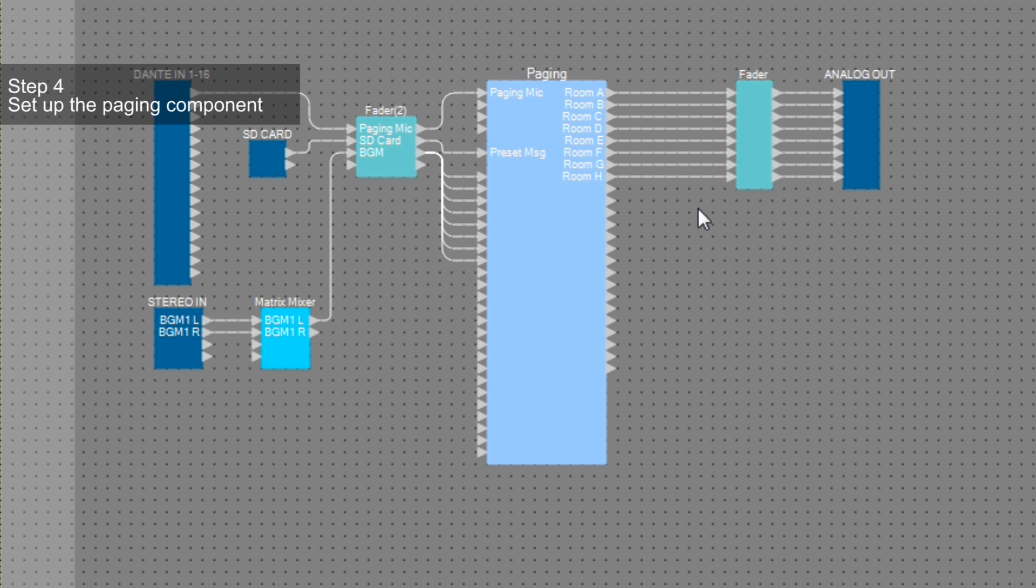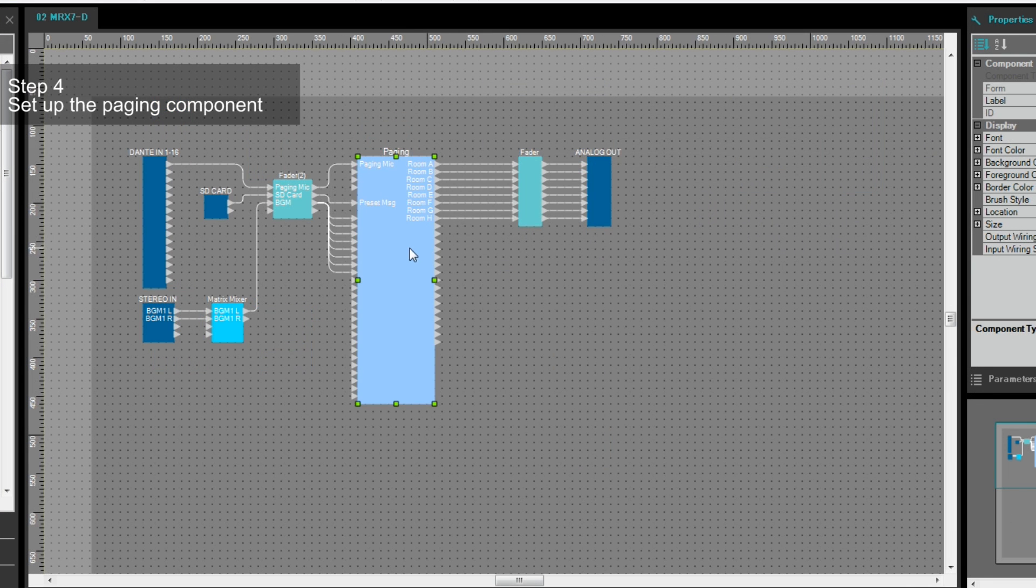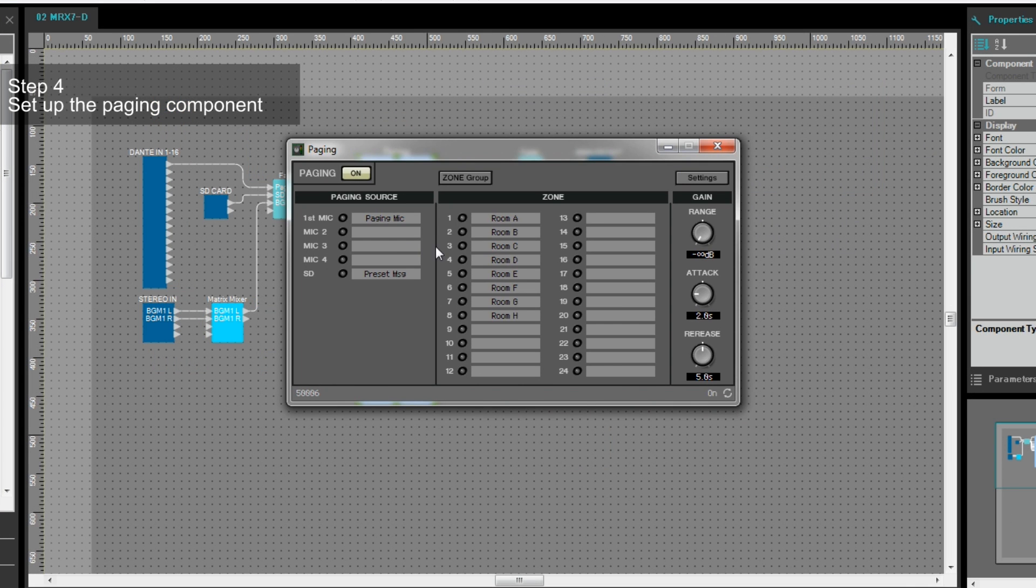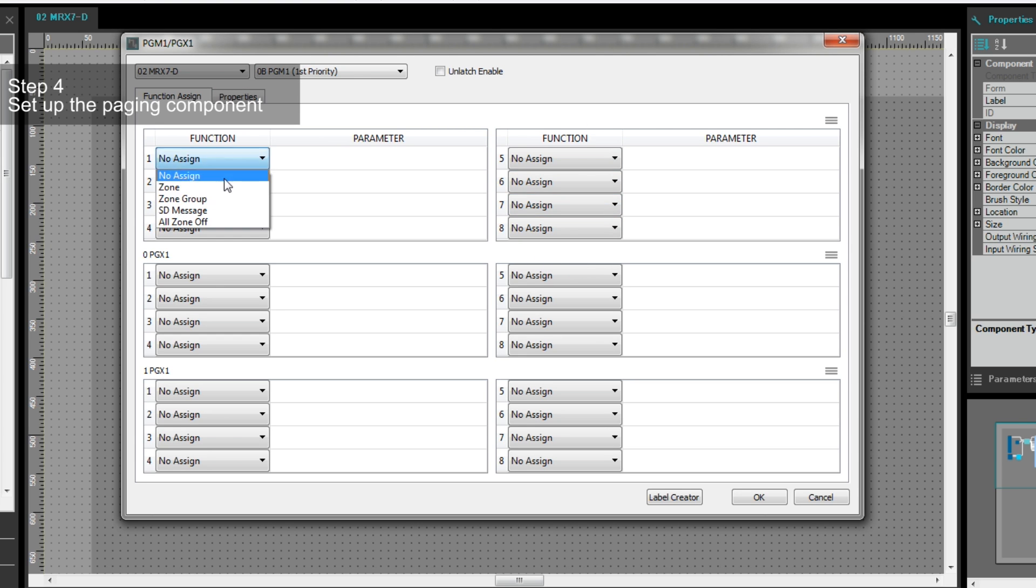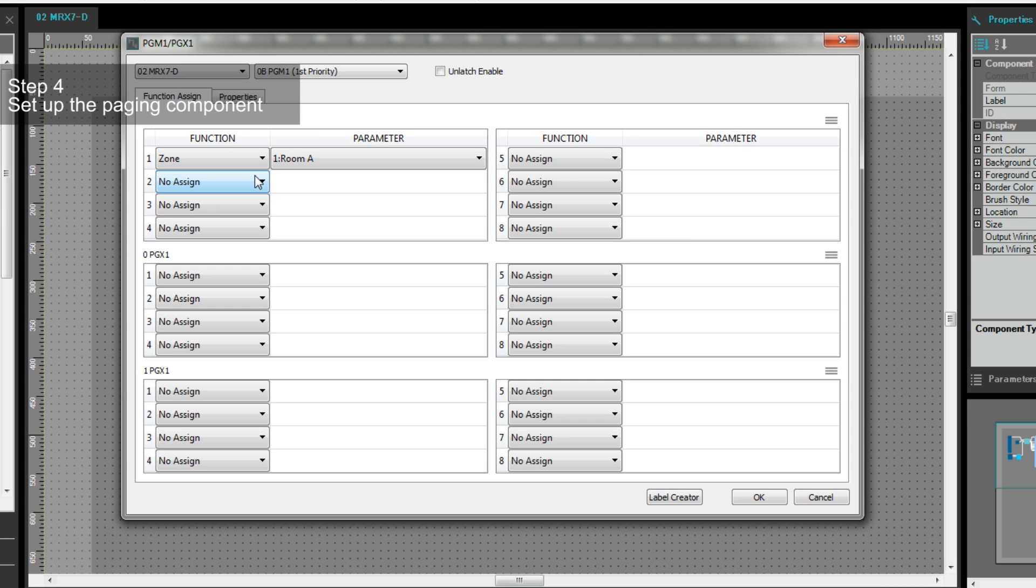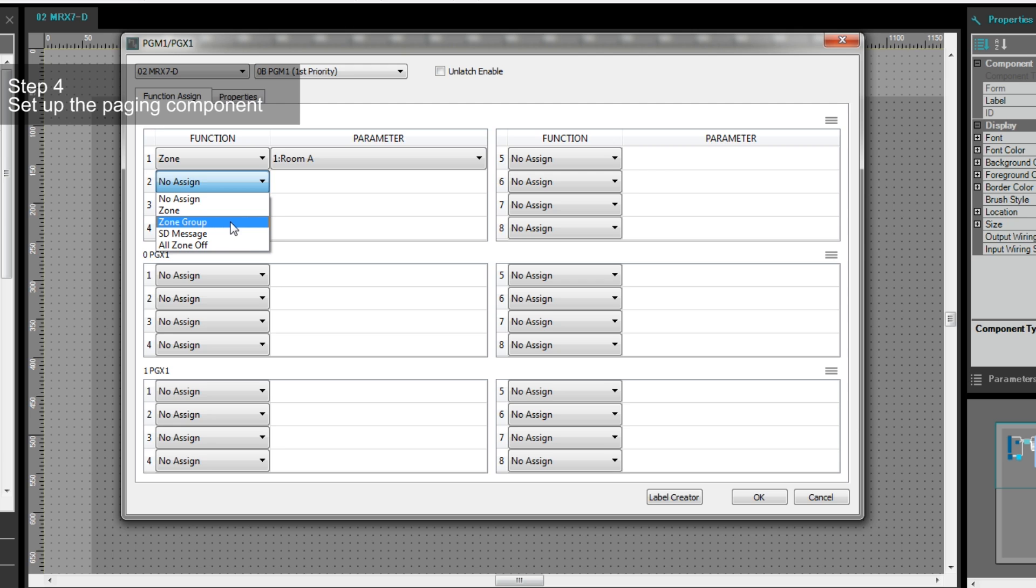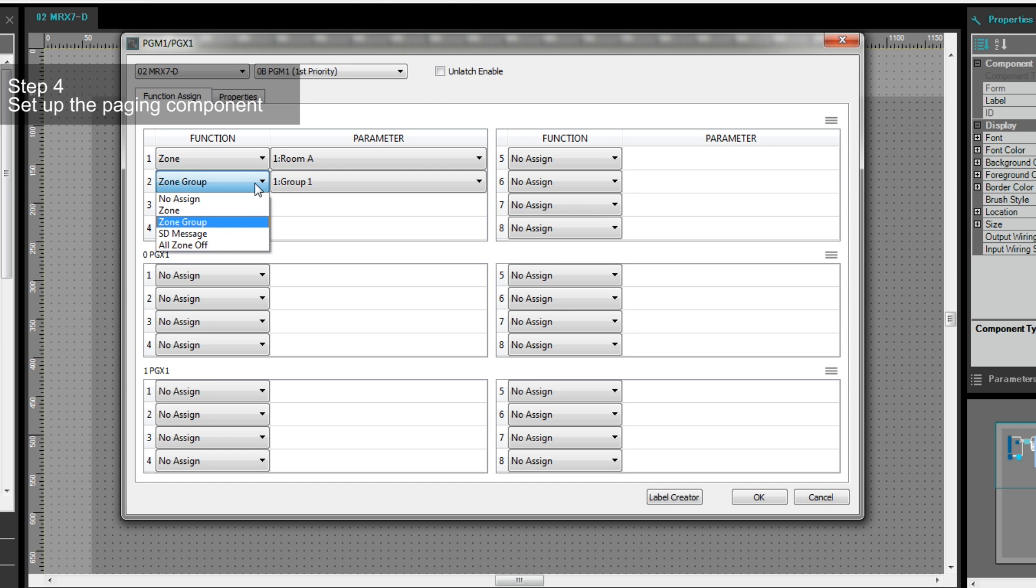Next, we'd like to set up the paging component. Double click to open the paging component, then click Settings to assign the command to each button on the PGM-1 and PGX-1. Here, we can assign the command to activate the paging function to each zone to a different button. We can also use Zone-group to activate paging functions to multiple groups at the same time.